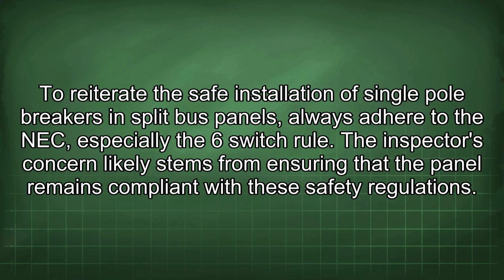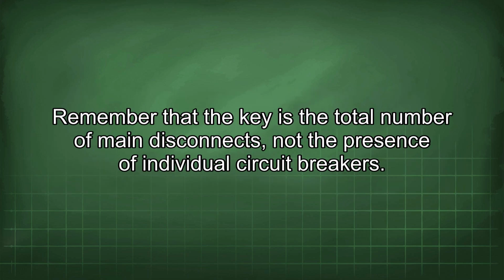To reiterate the safe installation of single-pole breakers in split bus panels, always adhere to the NEC, especially the 6-switch rule. The inspector's concern likely stems from ensuring that the panel remains compliant with these safety regulations. Remember that the key is the total number of main disconnects, not the presence of individual circuit breakers.